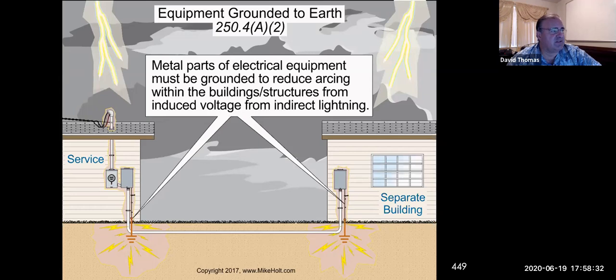Our conduits act as a big inductor. They also act partially as a capacitor because of the insulation between the wires. We have two conductive objects, which is the conduit and my copper wire, and then we put a dielectric in between there, which is the insulation. So there is some form of capacitance, but it's not that big of a deal. It's not something that we get concerned with, but because of capacitive and inductive effects, we actually have to be very careful to ground everything so it doesn't act as an inductor or as a capacitor, right? So, okay.